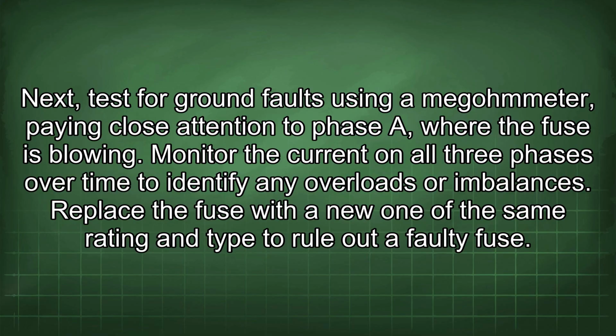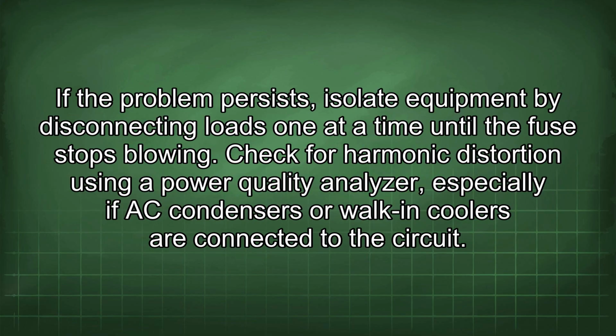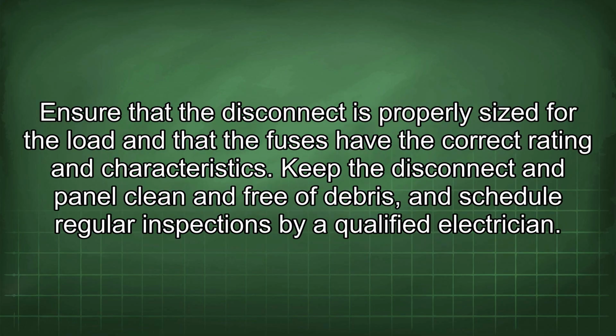Replace the fuse with a new one of the same rating and type to rule out a faulty fuse. If the problem persists, isolate equipment by disconnecting loads one at a time until the fuse stops blowing. Check for harmonic distortion using a power quality analyzer, especially if AC condensers or walk-in coolers are connected to the circuit.